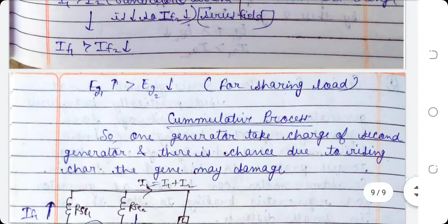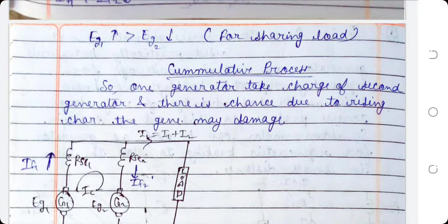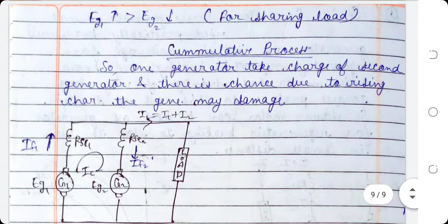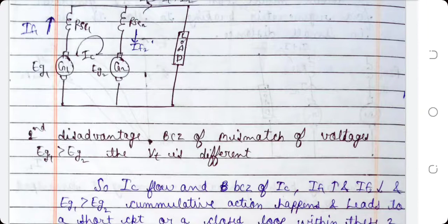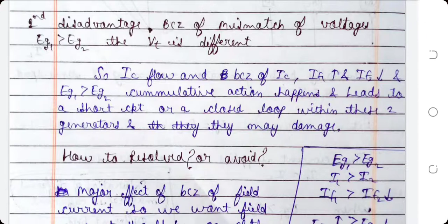So this is the cumulative process. One generator takes charge of the second generator, and due to the rising characteristics, the generator may get damaged. This is the diagram for the cumulative process. The second disadvantage is that because of the mismatch of voltage, Eg1 is greater than Eg2, Vt is different, so the circulating current IC flows, and because of IC, IF1 increases and IF2 decreases, so Eg1 is greater than Eg2. Cumulative action happens and leads to a short circuit, or a closed loop within these two generators, and they may get damaged. So how do we resolve or avoid this?